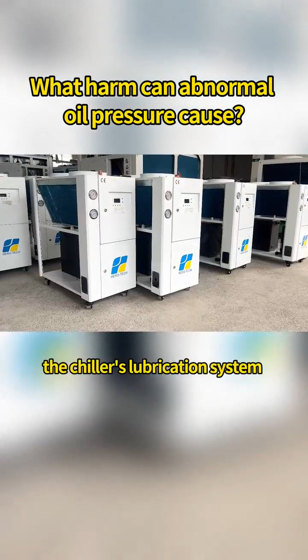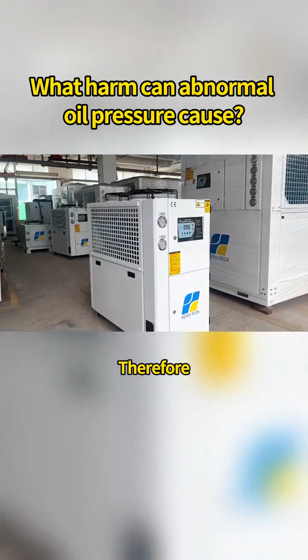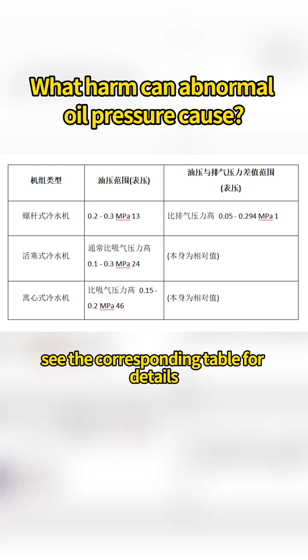If the oil pressure is insufficient, the chiller's lubrication system will not be able to provide sufficient lubrication and cooling oil, and even the power required to operate the energy-regulating device will be affected. Therefore, the oil pressure in the chiller's oil system must be maintained within a reasonable range. See the corresponding table for details.